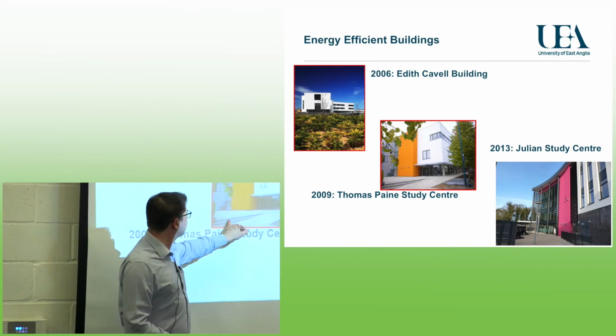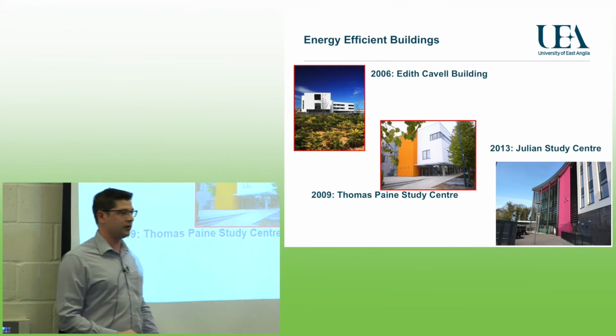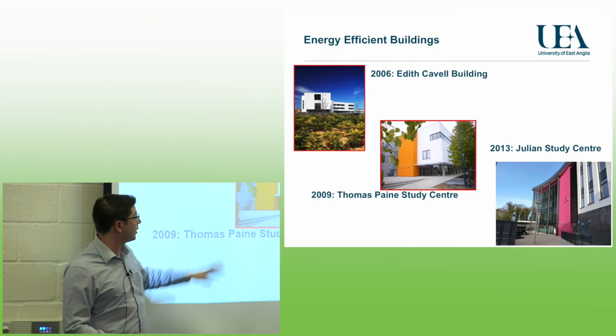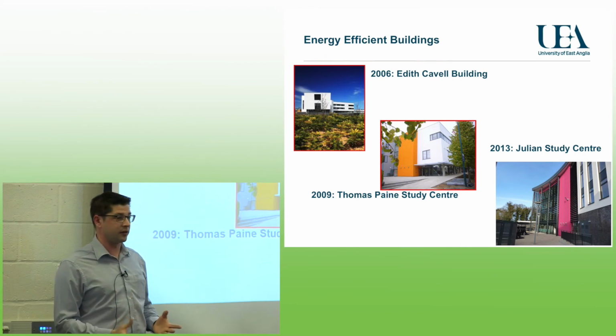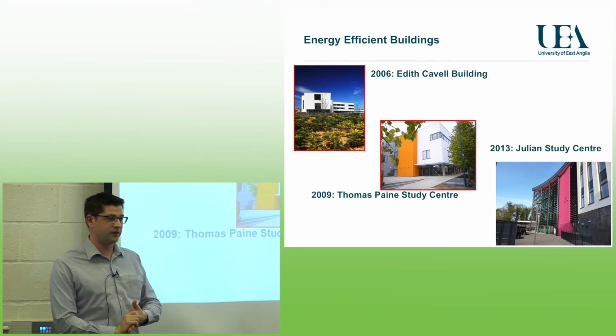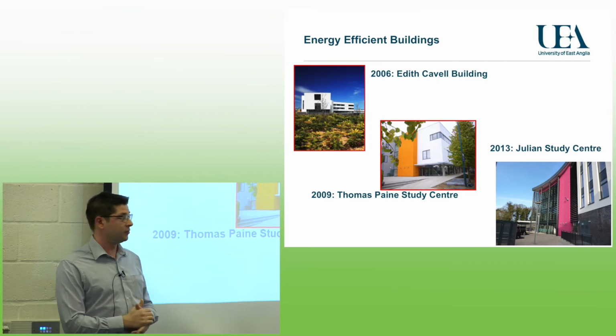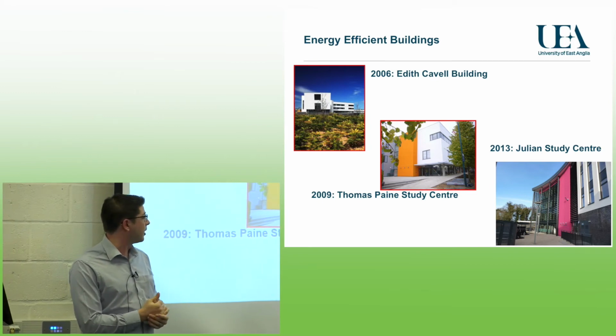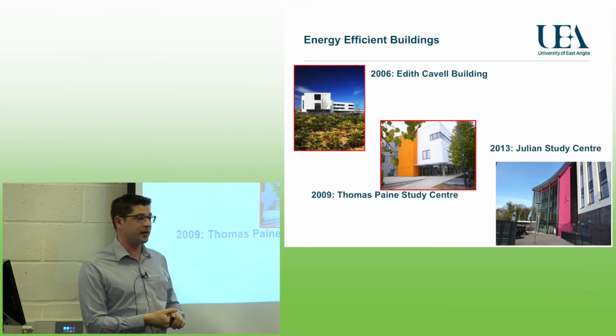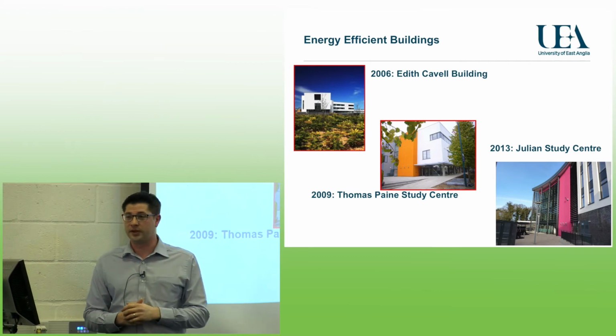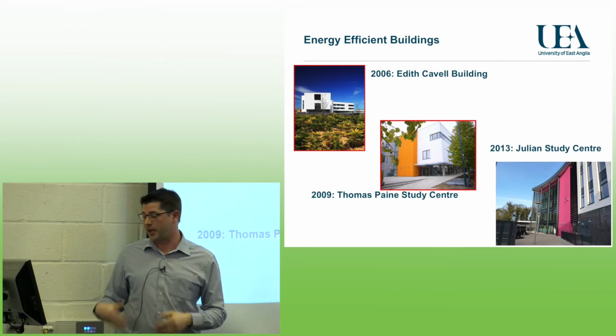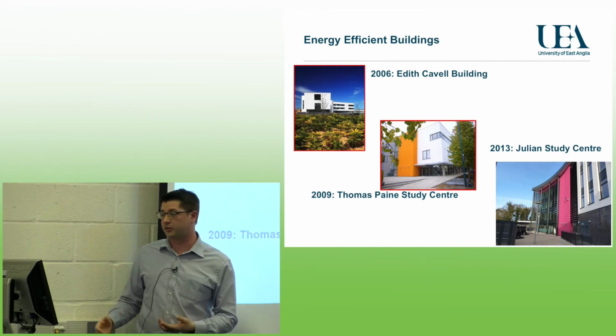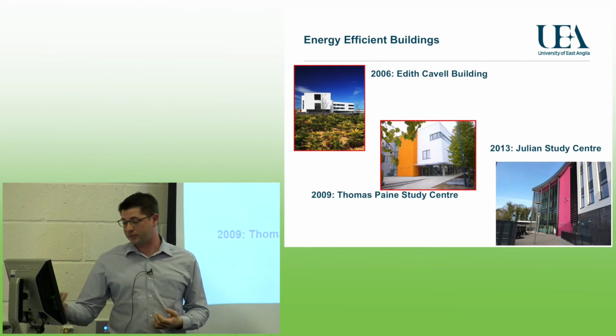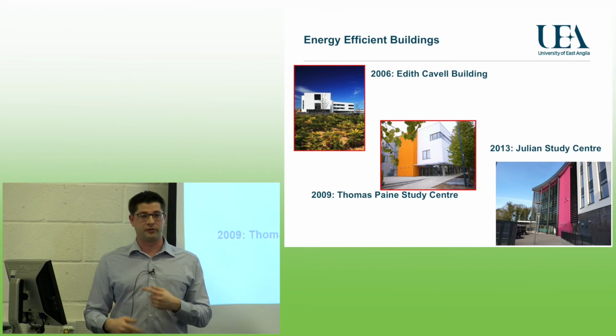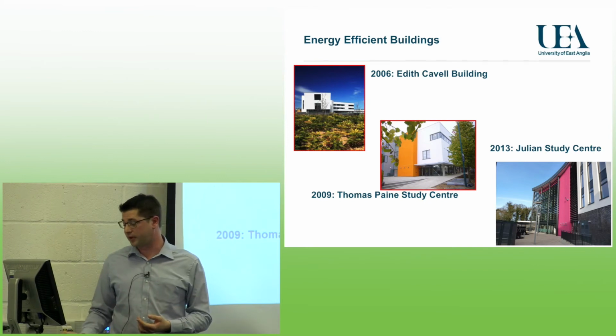In 2013, the district heating system between the Estates building and Thomas Paine had a leak, so we had to shut it down in March. It was -10 outside, and we had to shut it down for two weeks. We turned off the ventilation, and we had no complaints, nobody moaned, and we didn't have to install electric heaters. The heat from the computers and the people in there kept the building sufficiently warm. The reason we have to provide heat is because we also have to change the air, and that's the only reason.